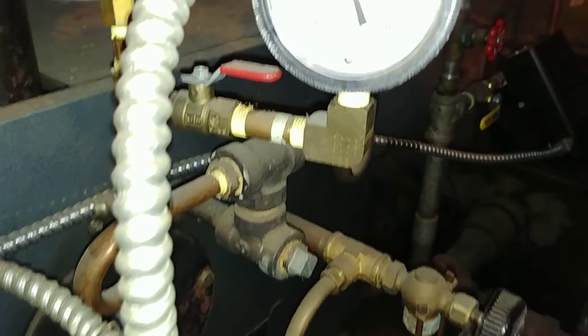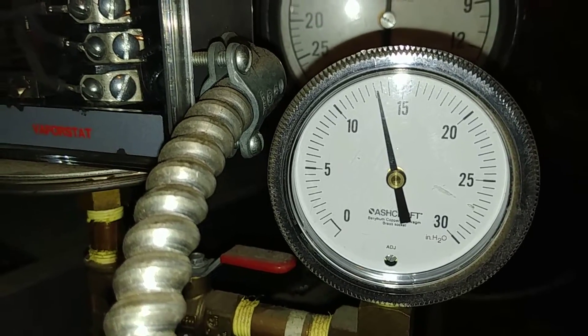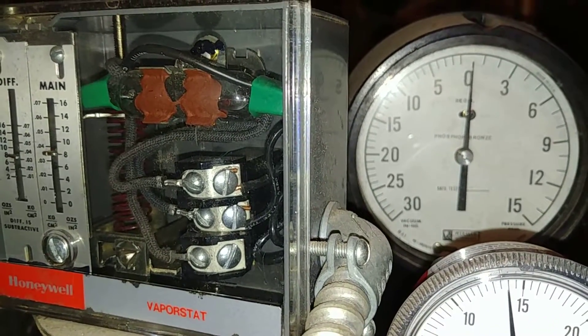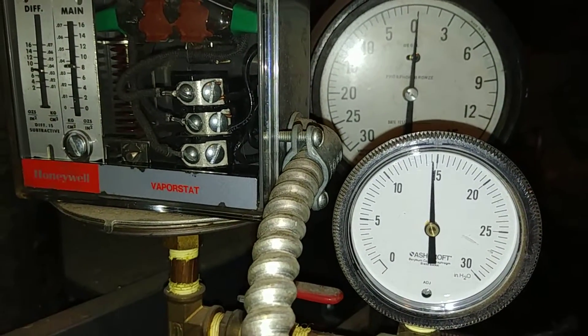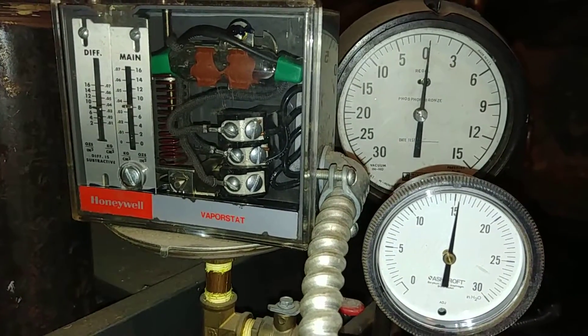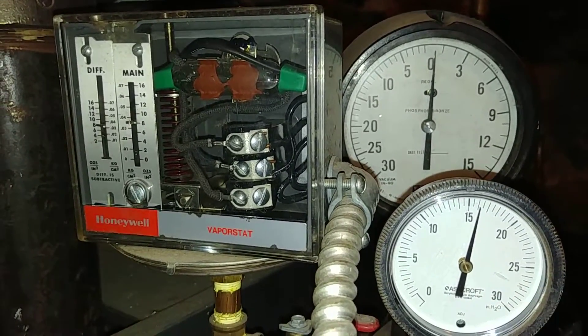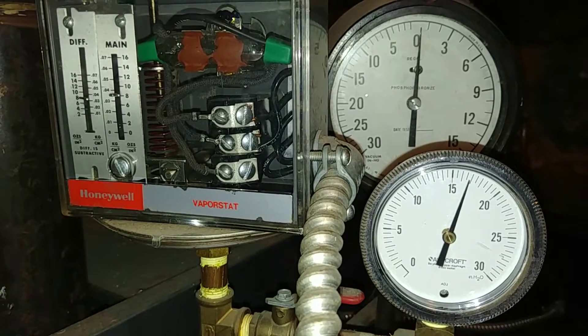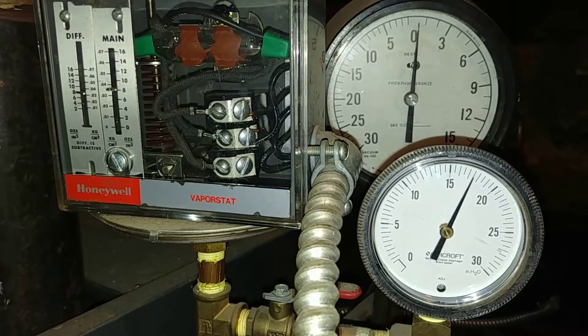The pressure is going up, and that's probably going to trip over in a few minutes. I don't know how much patience you all have to watch this. You can see it's really cramming the steam into the system much faster than it is being ejected — it's a fairly warm day.